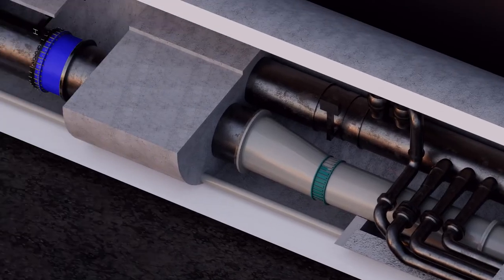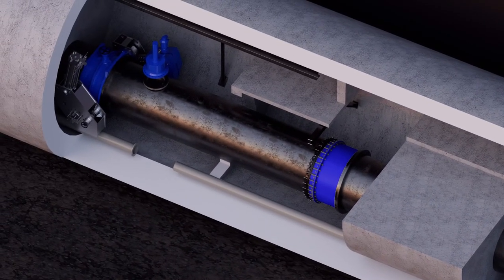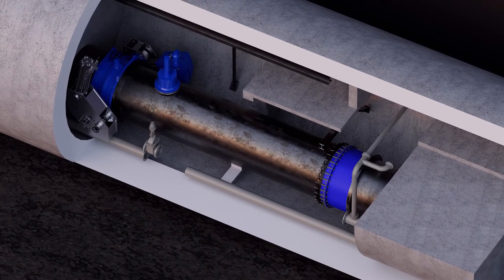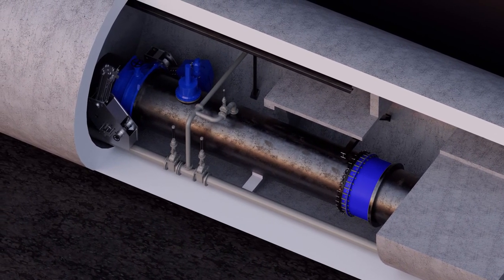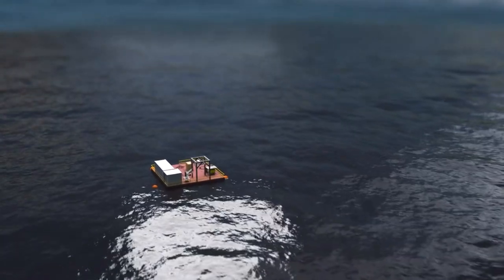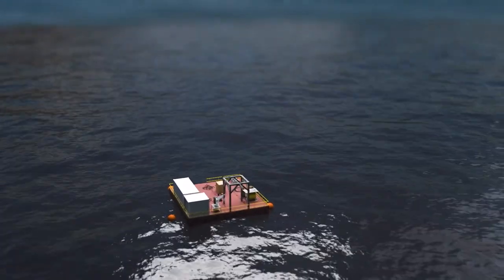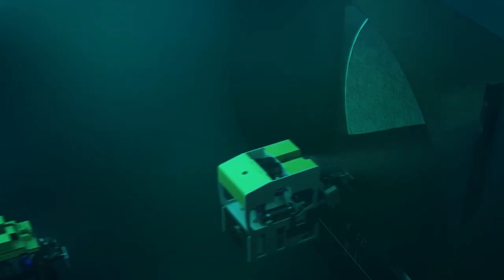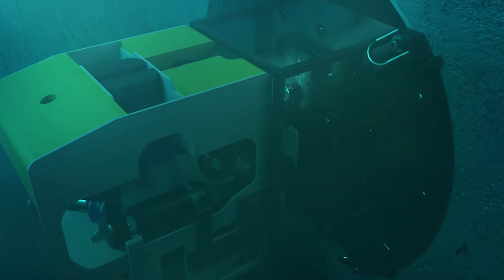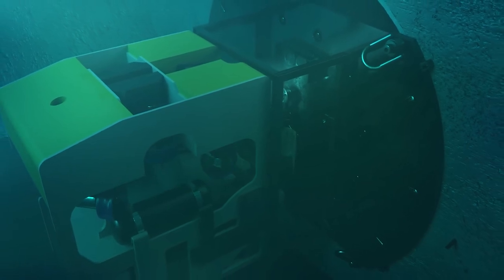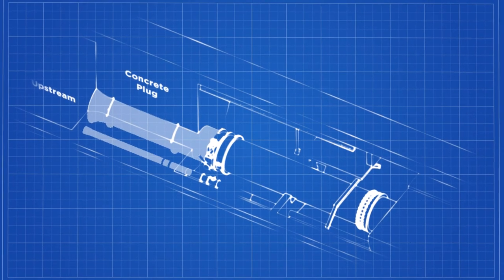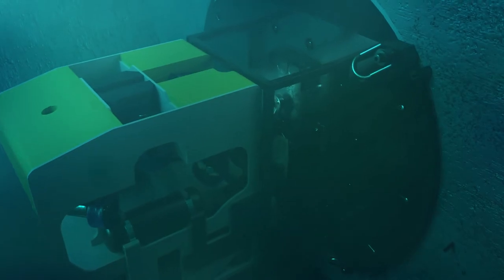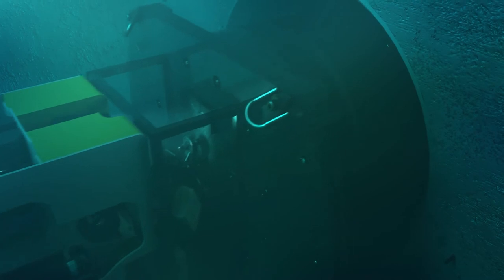Back up in the guard valve room, sections of the 12-inch and 6-inch piping were replaced and final touches were added. The ROVs returned to the tunnel to open valves that allow water to pass through each of the isolation barriers, flooding the space between the isolation barriers and the new valves. With the pressure across the isolation barriers balanced, the isolation barriers were removed.